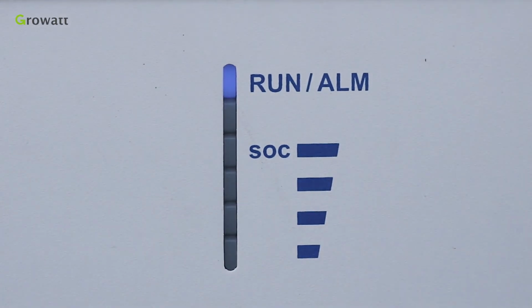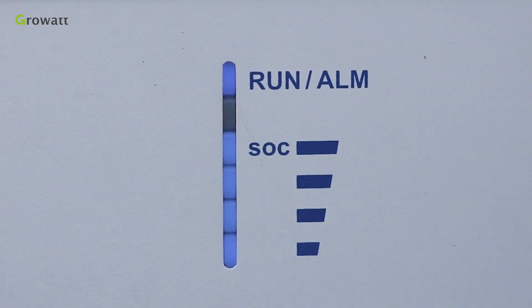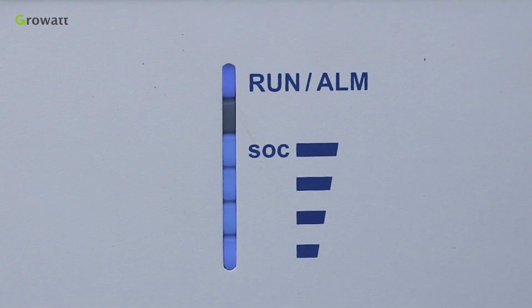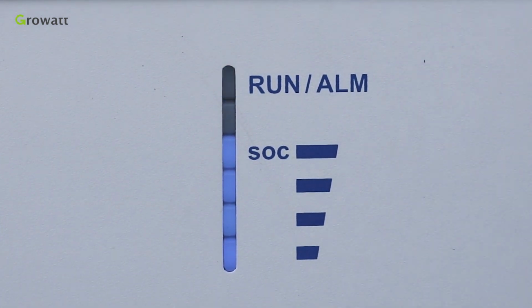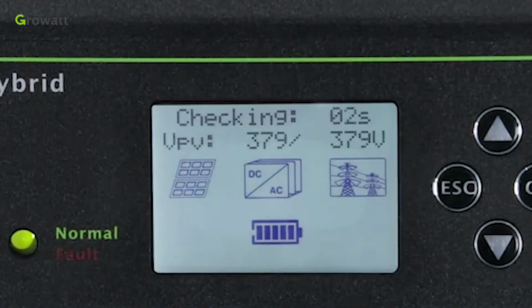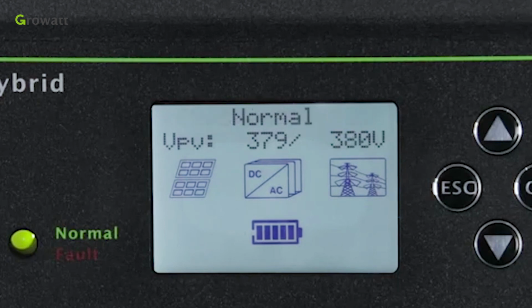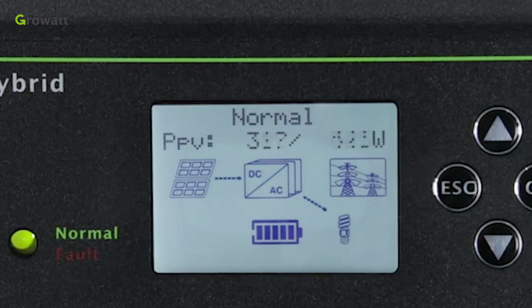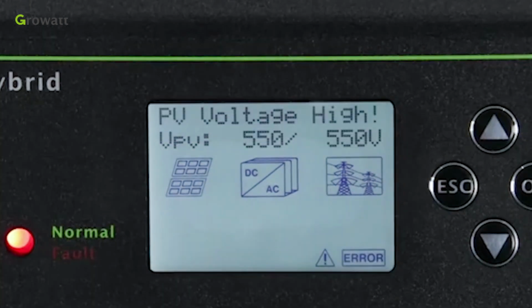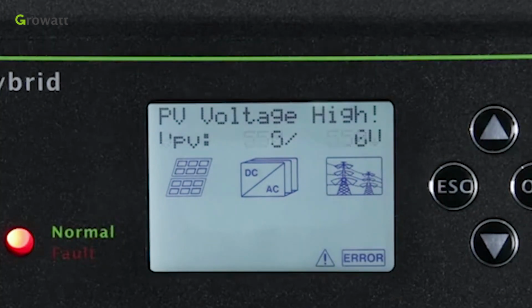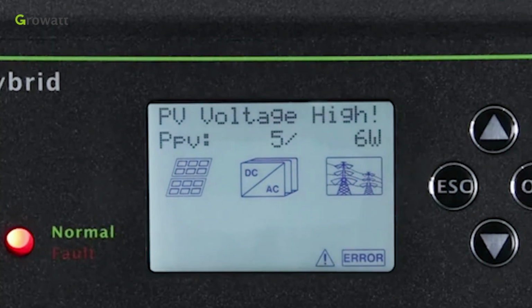If the run light on both batteries flickers 5 times, it means that the two battery systems power on successfully and the communication between the two batteries is good. If the alarm light of the battery turns red, it means that there is a parallel failure and it should be fixed before powering on again. After the system is powered on, if PV, grid, and battery are available, the system will work in normal mode. When the SPH is in normal mode, the screen shows normal and the LED is green. If SPH didn't enter normal mode successfully, especially if the LED is red, please contact Growatt service engineer for help.